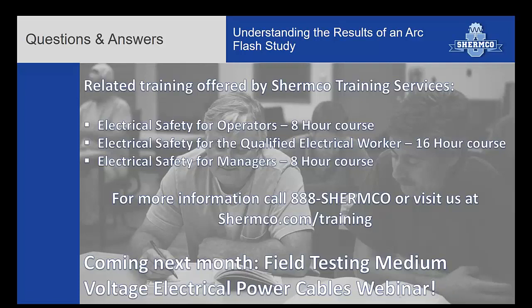Everything is always based on the assumption that the switch was installed properly per manufacturer. It is not in an impaired condition. It has been maintained. And that kind of goes with any of the energized work. I mean, all of these studies that we've talked about here is really on that magical assumption. It's been maintained. Breakers have been lubricated. No additional friction in their operating times or anything like that. So that always has to be taken into your feasibility risk assessment is, how well have I kept up on the gear? Okay.